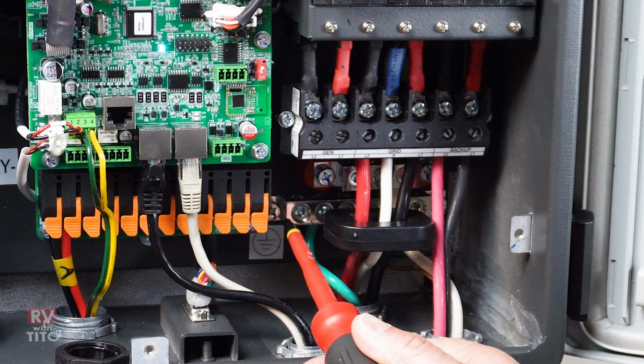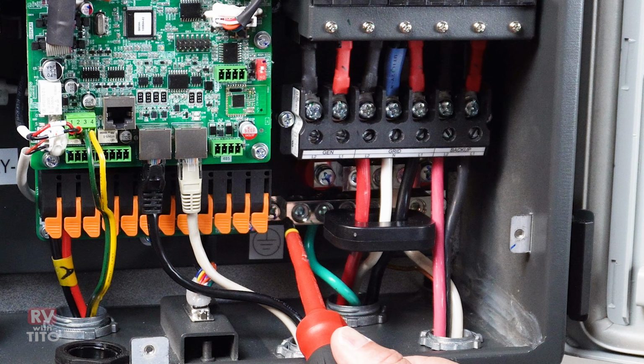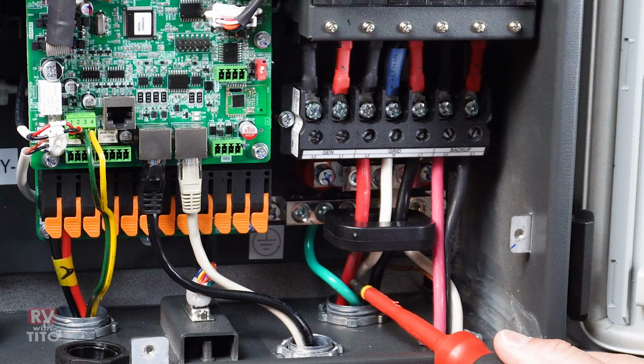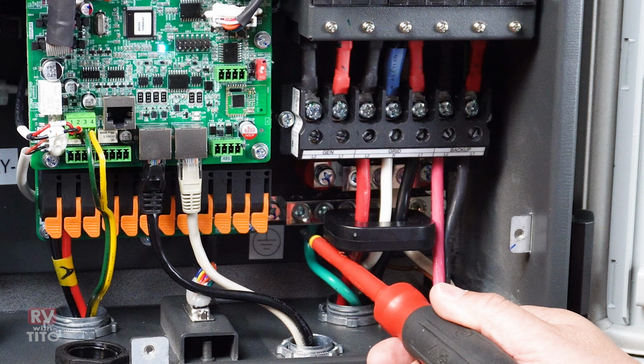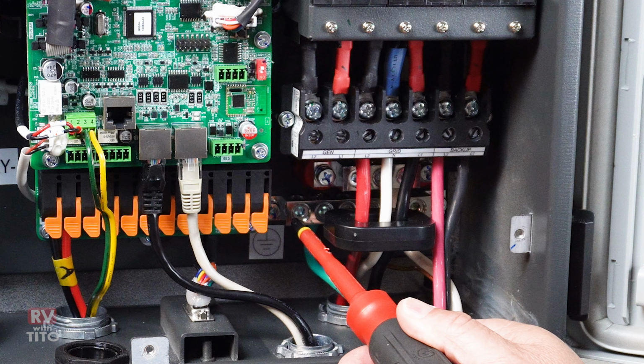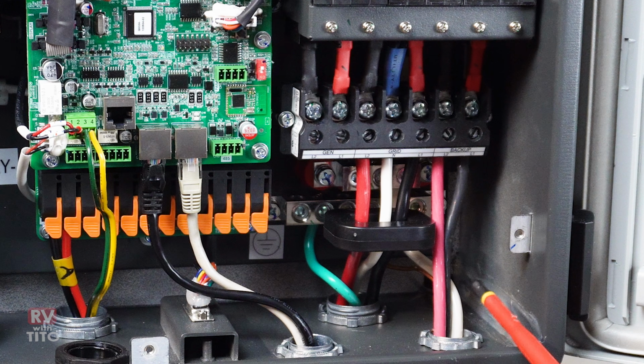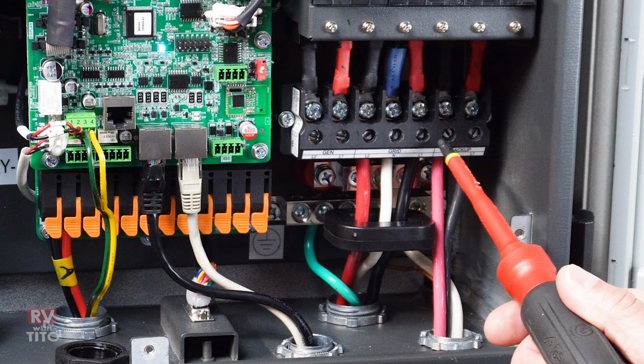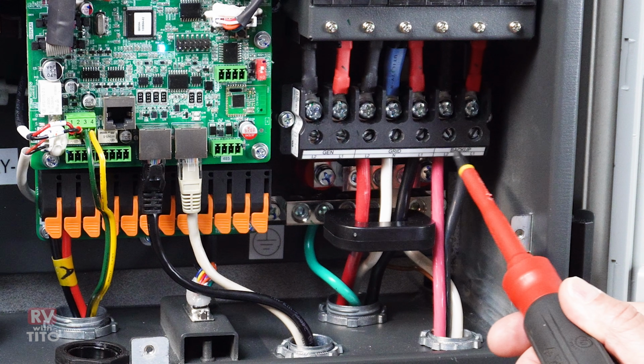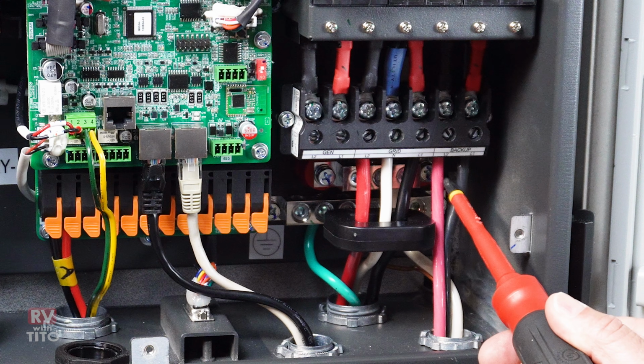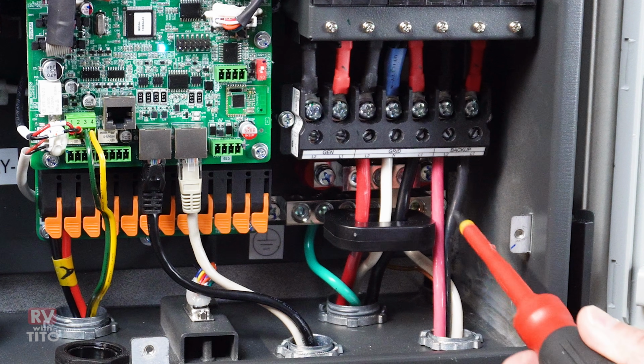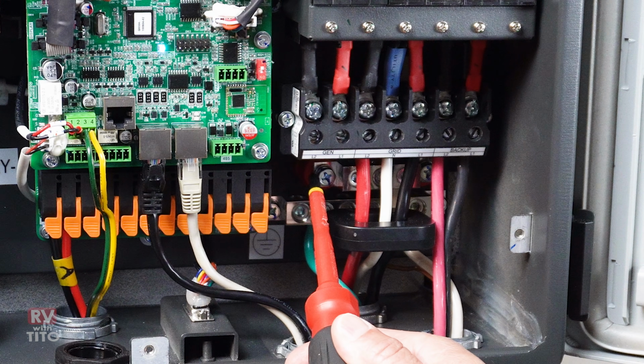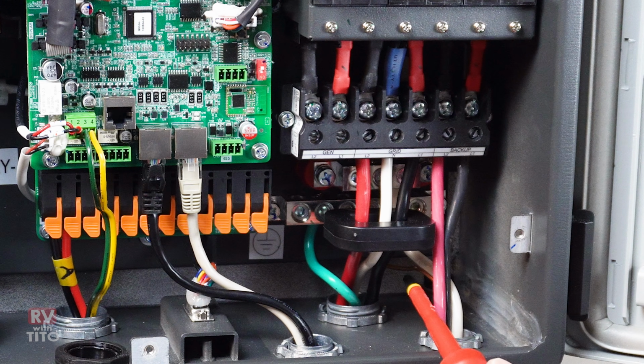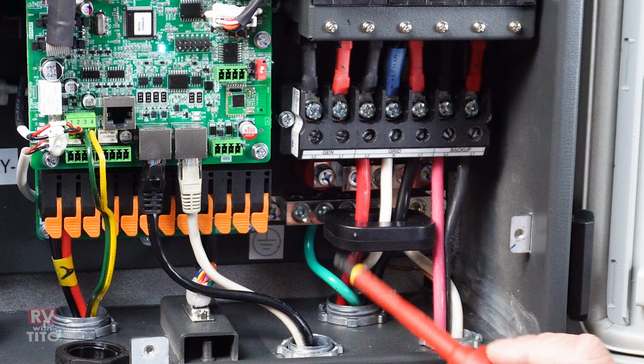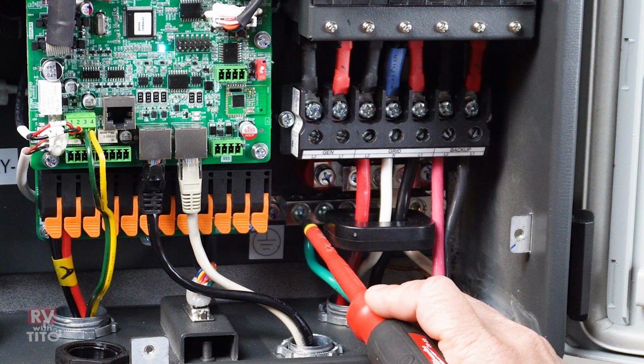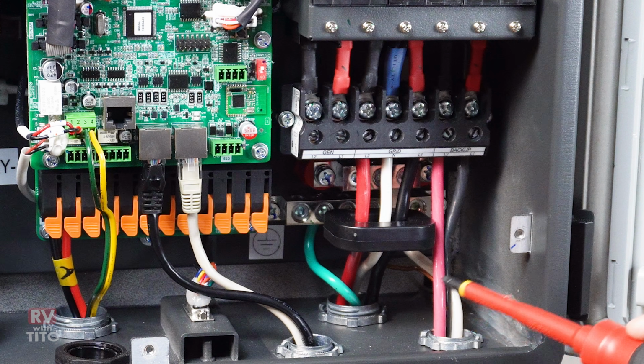And then we also have a grounding bar back here. So the ground for the grid connection is grounded to this grounding bar back here, which is where all the other grounds would be. If we look at our output here, which is our split phase output on our backup, we've got an L1 and an L2, and then the neutral is connected to this neutral bar here. And there's a copper grounding cable that goes to that grounding bar in the back. So that's the way that's hooked up.